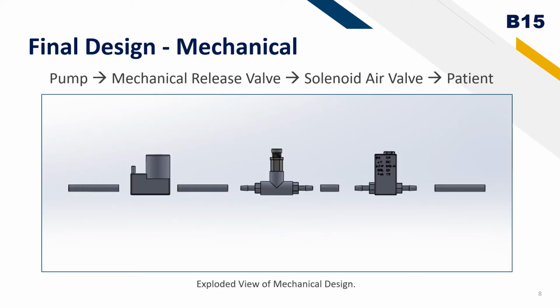The purpose of the mechanical design was to provide safe, reliable, and consistent airflow to a patient using constant pump flow. We achieved this with a 12-volt miniature diaphragm pump, which provides up to 5.5 liters per minute, enough to sustain a child under the age of 5. The final mechanical design involves the constant pump flow that provides air through a mechanical release valve, then solenoid valve, and then to the patient as displayed in the exploded SolidWorks view below.